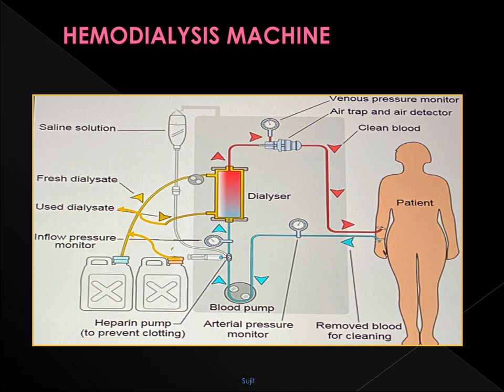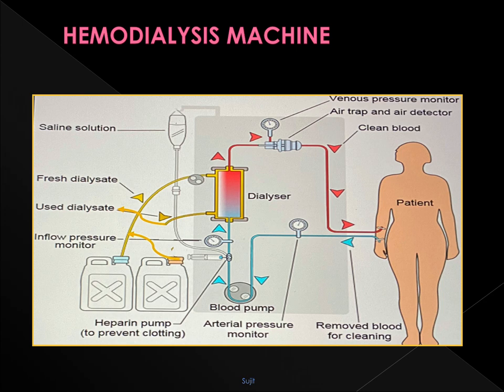This is the schematic diagram of a hemodialysis machine. The blood pump takes blood out of the body for dialysis. Since blood outside the body will clot, we use heparin to avoid clotting. We prepare dialysate from acid concentrate, bicarbonate, and reverse osmosis water. Diffusion, ultrafiltration, and convection occur inside the dialyser, and the dialyzed blood is returned to the patient. We must ensure no air enters the patient, so there is an air bubble detector and a clamp to prevent air from being returned.